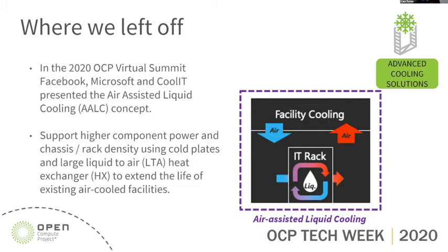While this does not capture the full benefits of direct liquid cooling, in that it still relies on the facility HVAC to remove the heat from the data center, it does offer to extend the life of the existing air-cooled facilities by supporting these higher powered liquid cooled SKUs from silicon vendors.